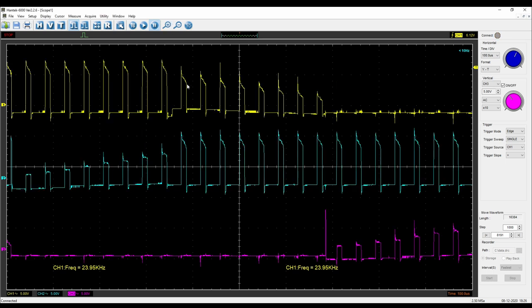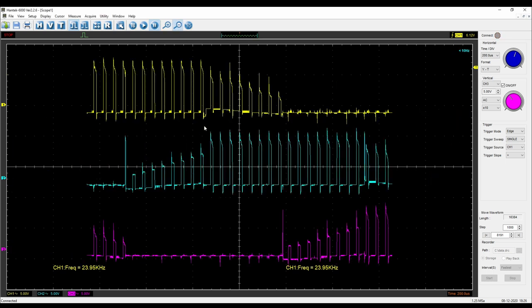So, as I've said earlier, this is how we create the AC needed for the motors to turn, and we create it by means of PWM pulses. Obviously, on one motor output, you have six switches, MOSFETs in most cases, and those six MOSFETs have a pretty complicated switching pattern, which I will not try to explain here. But if you are interested, you can search for an AC inverter schematic and how it works, if you are keen to find this out.